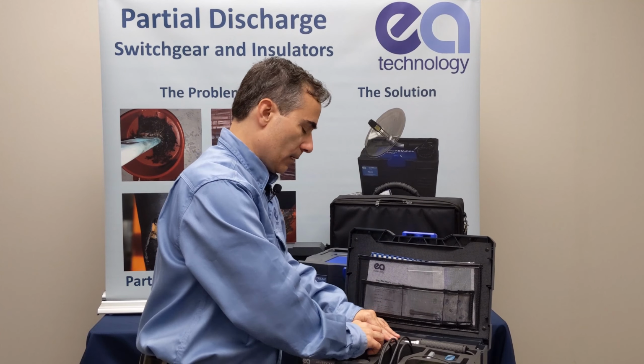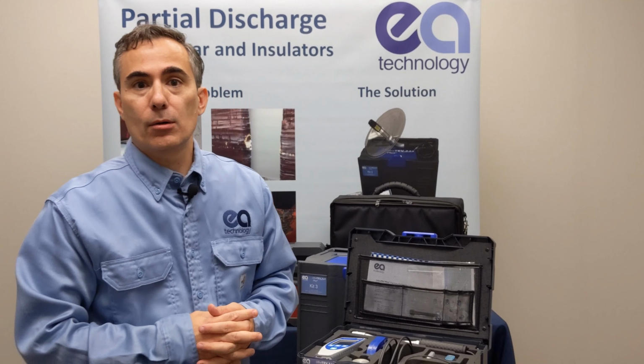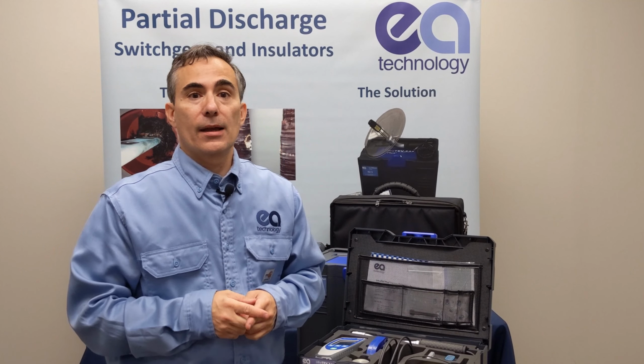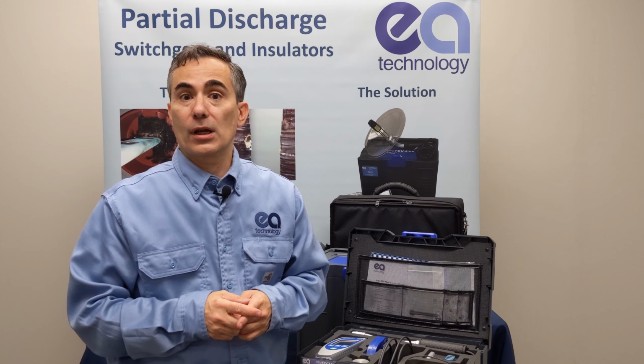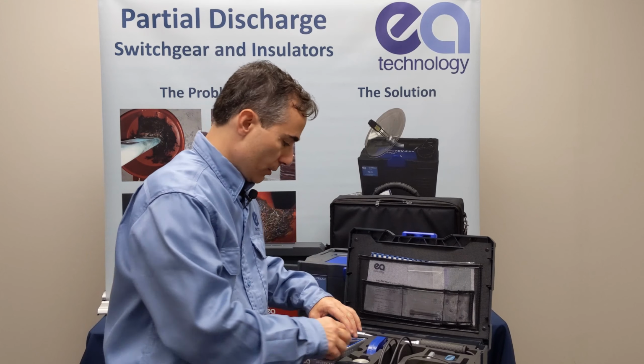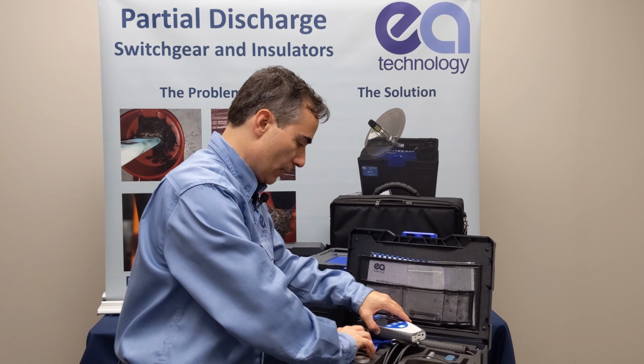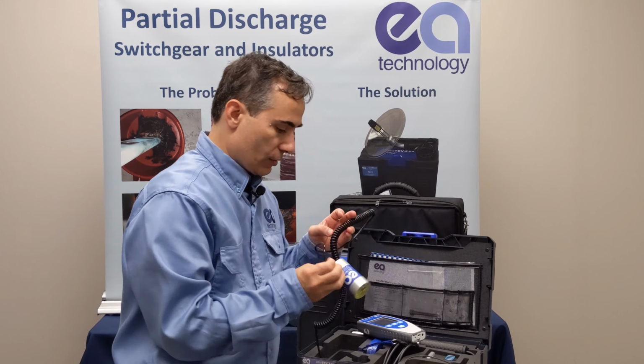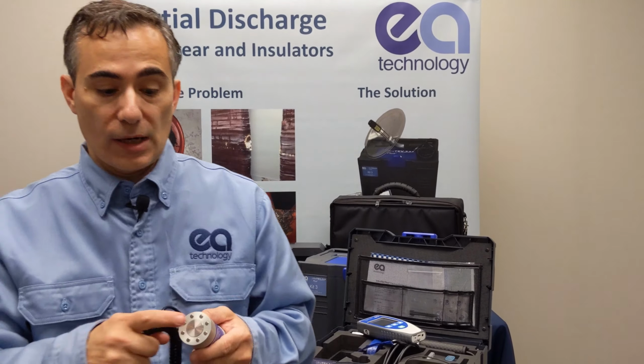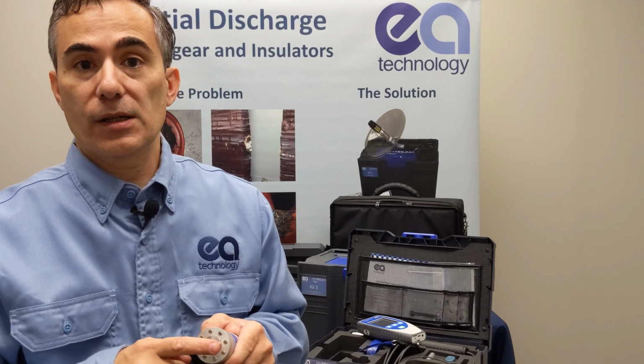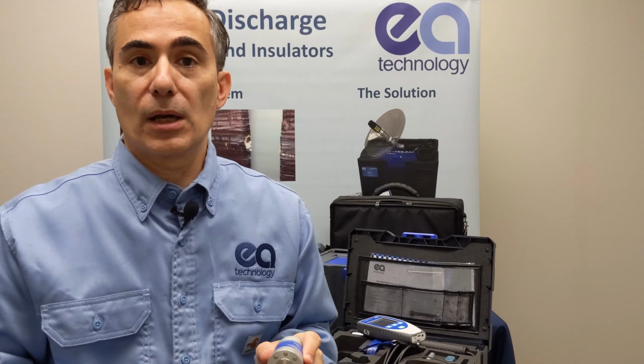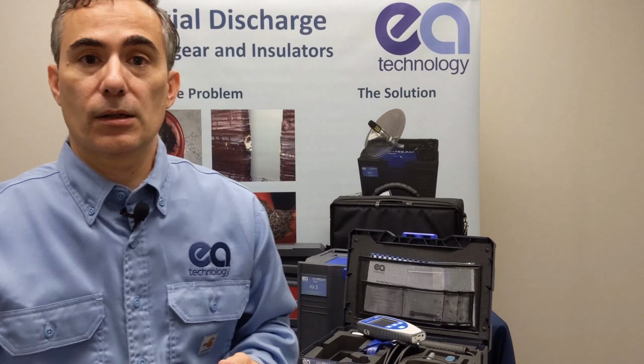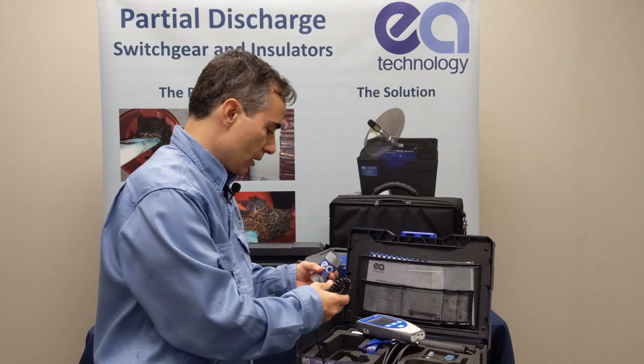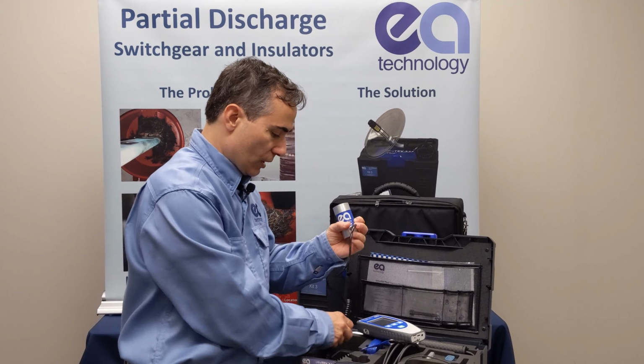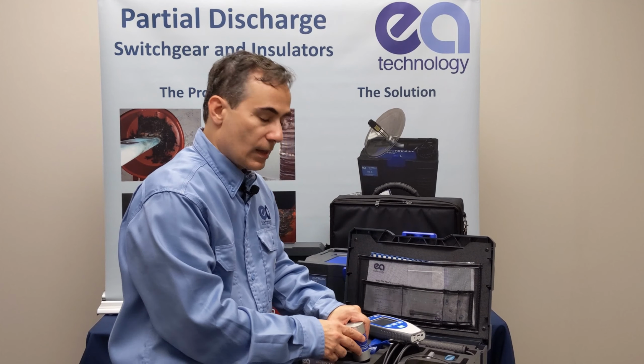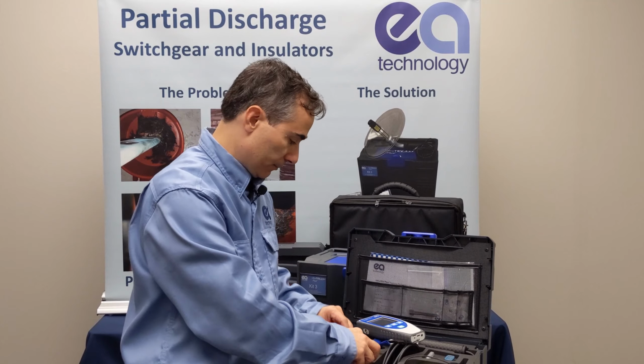If you have a switchgear cabinet or bus bar that's completely sealed with no path for the ultrasonic sound to get out, there's an additional sensor included in Kit 2, which is this one. It's an ultrasonic sensor with a magnetic face, so you just connect it to the metal surface, and it connects again to the UltraTEV. Each of these sensors, once connected to the UltraTEV, are recognized automatically by the instrument.